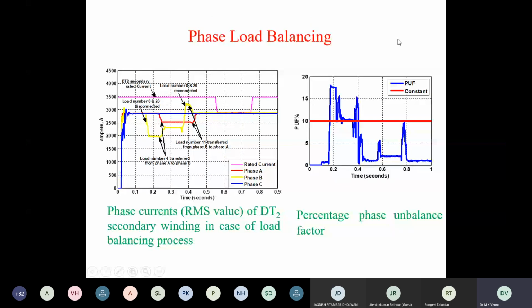He has calculated some factor which is representing phase unbalancing, the unbalancing factor. Whenever the phase unbalancing factor goes beyond 10%, phase load balancing is done. Here you see at this time the phase unbalancing factor has gone to between 15 to 20%, more than 10%. So what is done? The load balancing algorithm was run, and based on that, at this point you see load 8 and 20 are disconnected to make the loads balanced, and then the unbalancing factor comes back to less than 10%. Again, it is connected at some point.